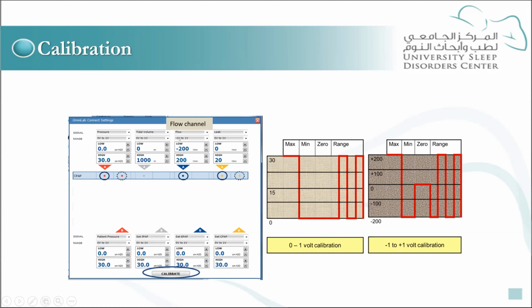Then you have the flow channel. Flow has inspiration and expiration, so it's minus and plus. When you do the calibration, you need to use not the 0 to 1, but the -1 to +1 volt port. This is the 0 line, which is when the patient is not breathing, and -200 and +200 liters per minute is equivalent to +1 and -1 volt.